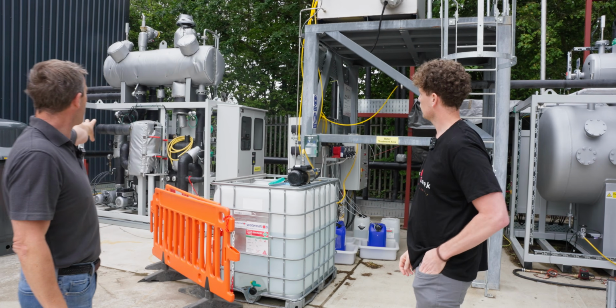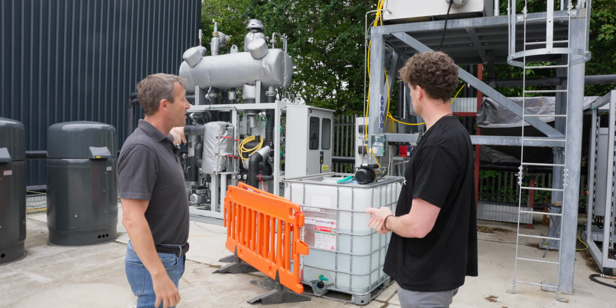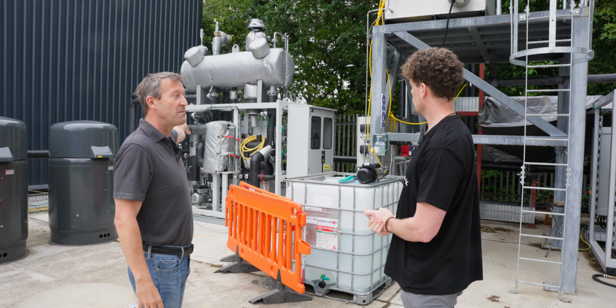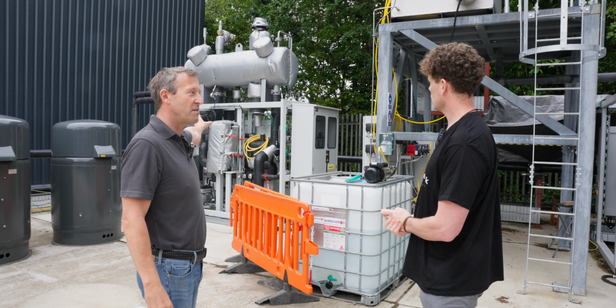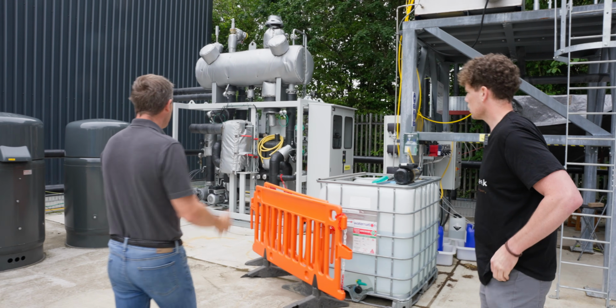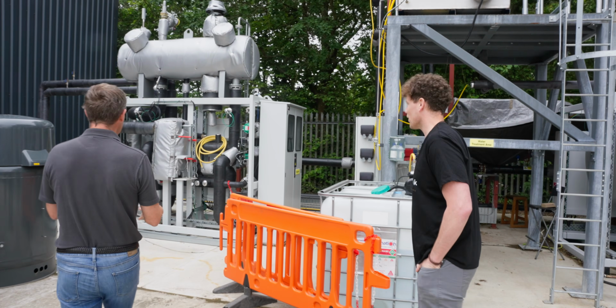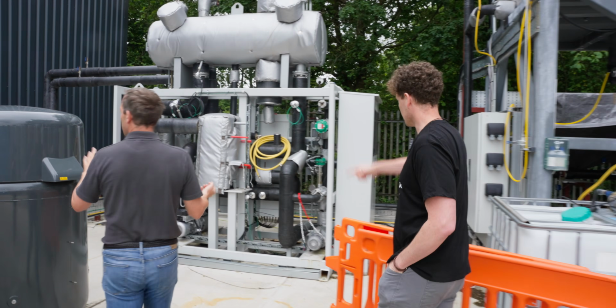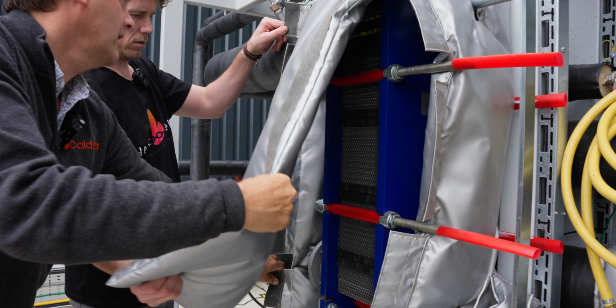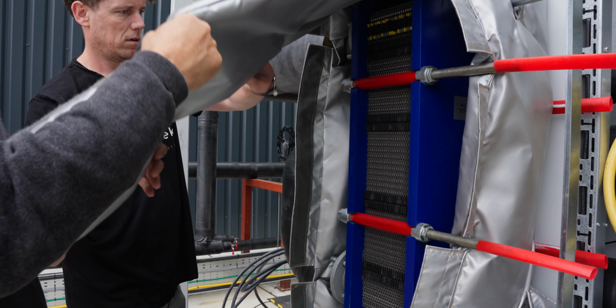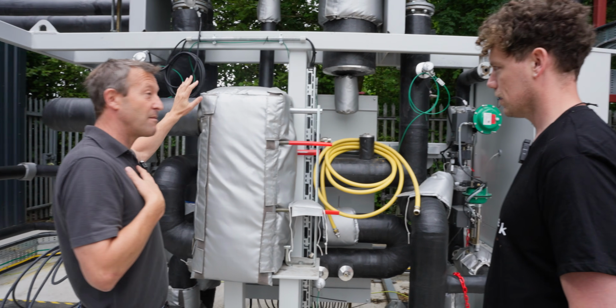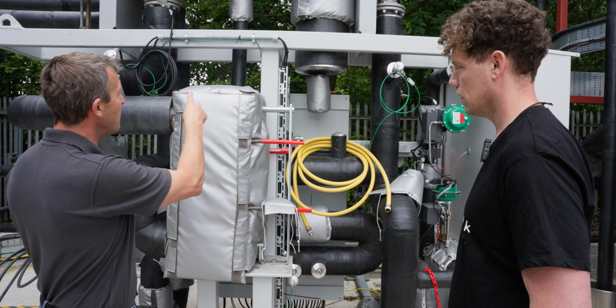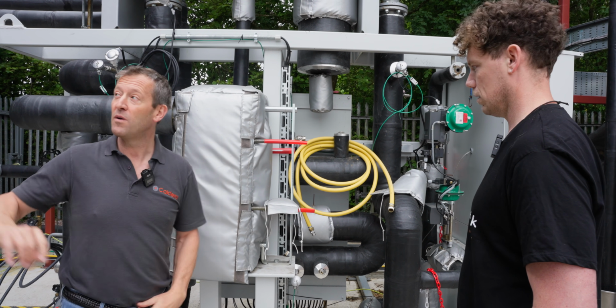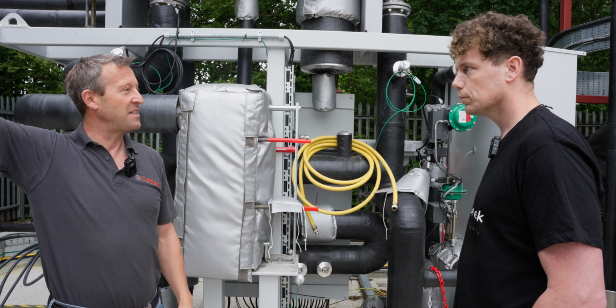On this side, the second way we have of heating is we can take steam to a plate heat exchanger and just heat water, like a big version of what we do in the home units. Steam comes in one side from our side, all nice and clean, comes out as water, and we pump water through the other side from the tank. So we've got two ways of heating the tank, one is just to take water out and run it through here, and it comes back at 90.